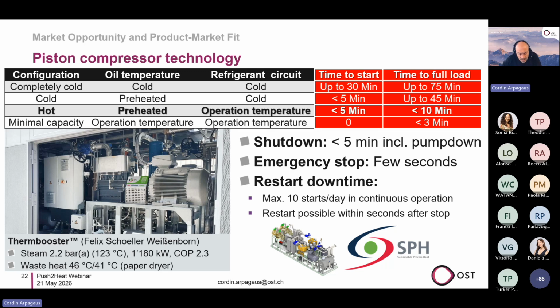So here we can see the time scales for startup or to reach full load operation. Look at the red columns there. If the heat pump is hot and the oil in the compressor is preheated and the refrigerant circuit is already warm, it takes only a few minutes to full load, maybe 10 minutes or 3 minutes. So it's a very flexible technology with this piston compressor technology, and this offers a technical advantage. For example, the shutdown is in 5 minutes, emergency stop in a few seconds, and yes, it can start several times per day.